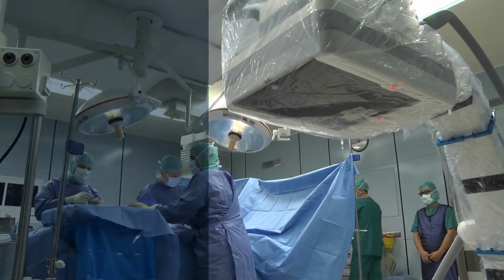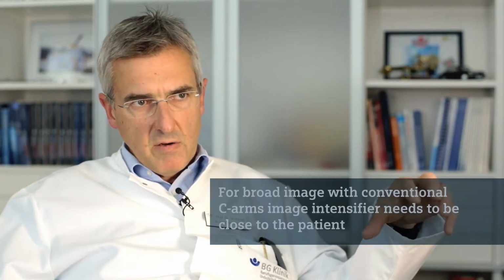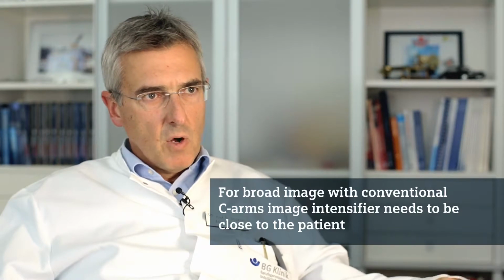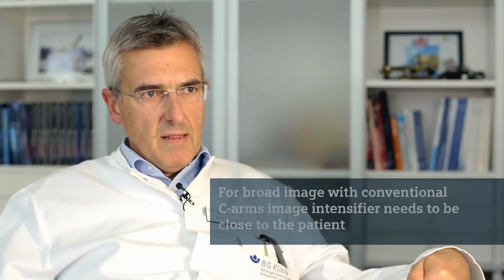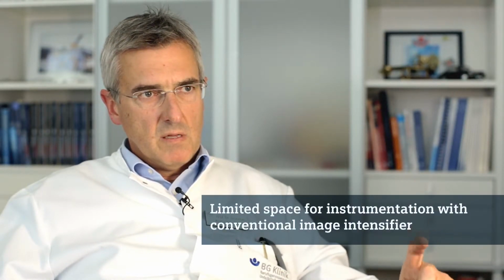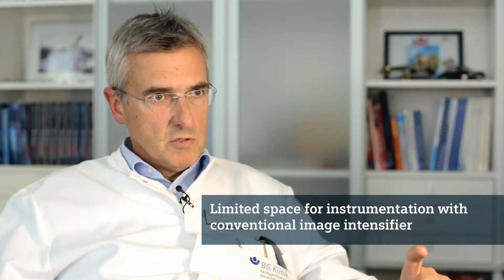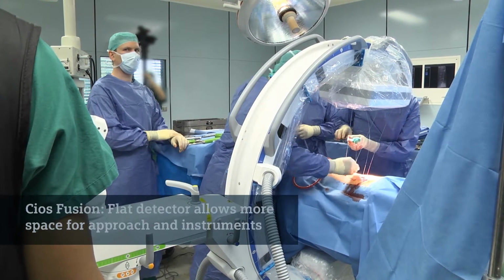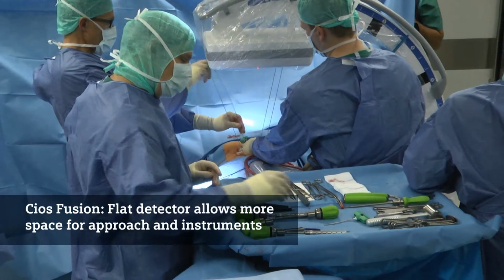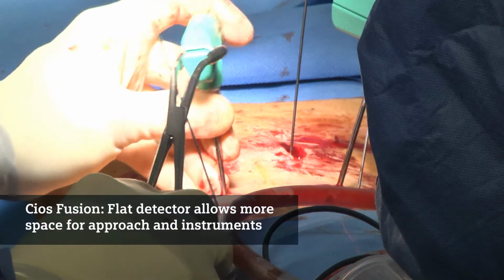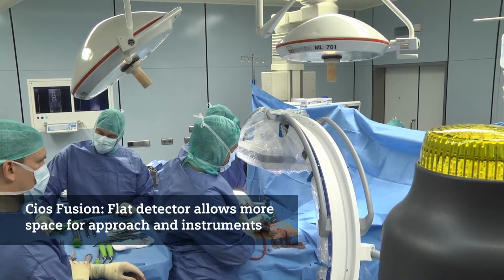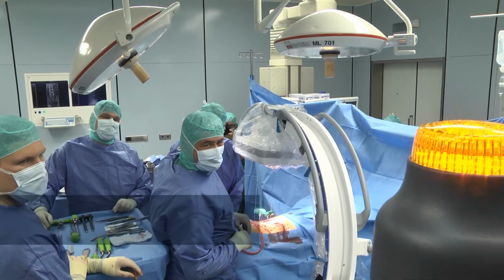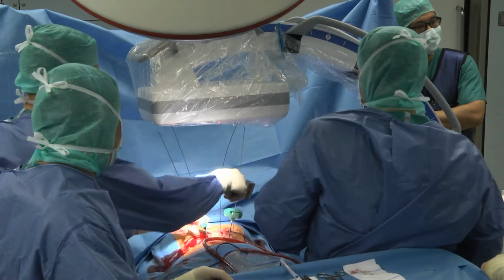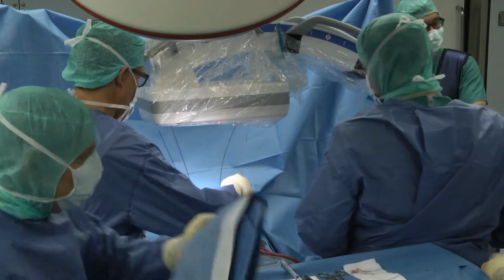In a conventional C-arm you have to move the intensifier very close to the patient to get a broader image. And that means you have a very narrow space between the approach to the patient and the image intensifier. With a flat panel you have more space between the approach to the patient and the C-arm, therefore you can much easier position your targeting devices, your instruments and so on. So that's really the difference.